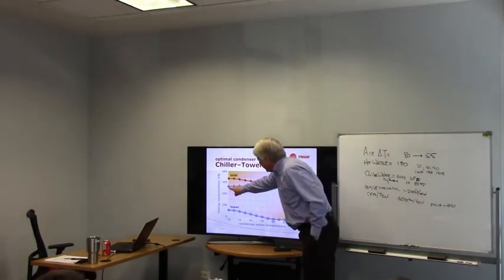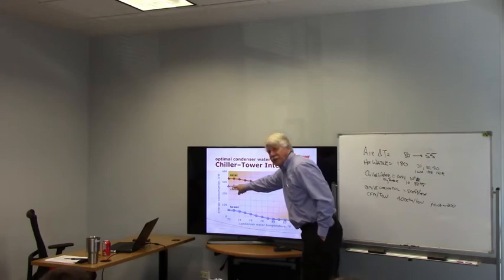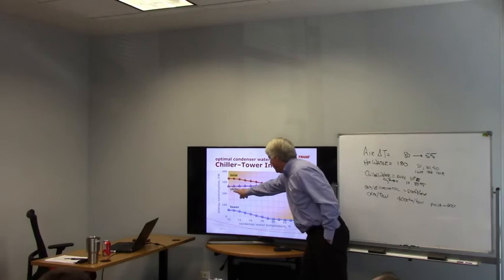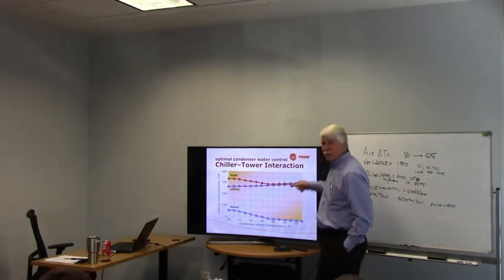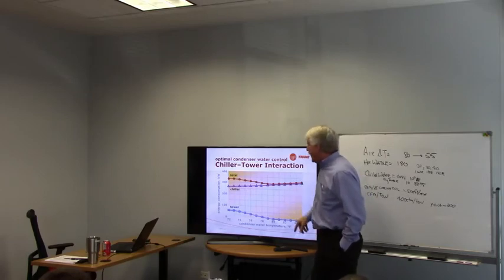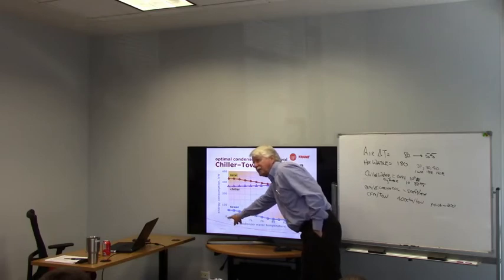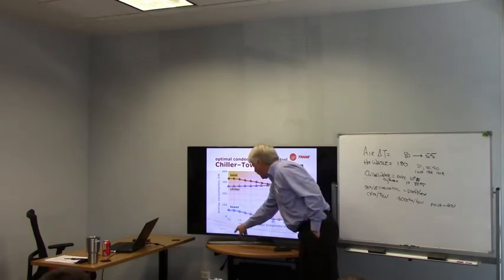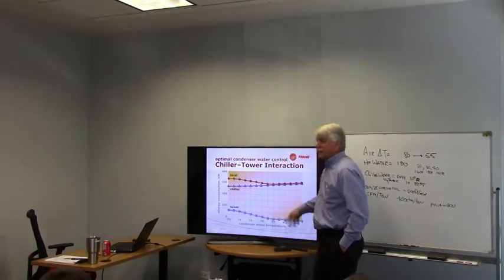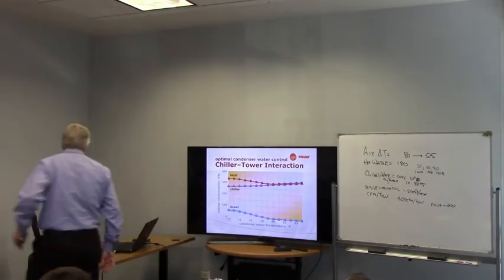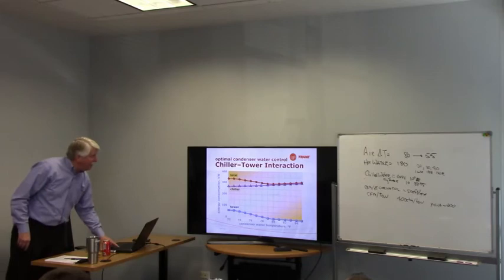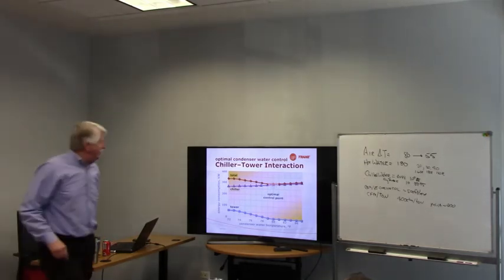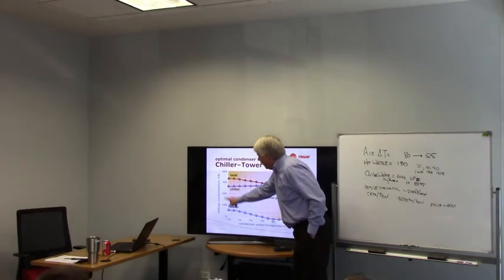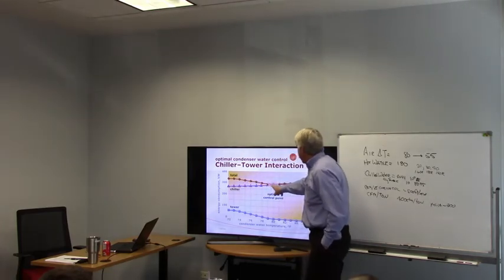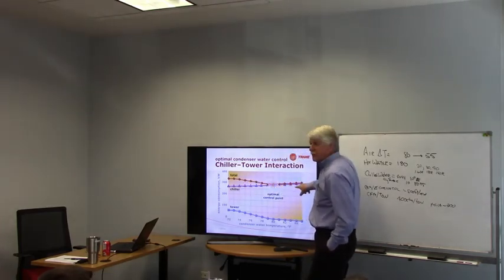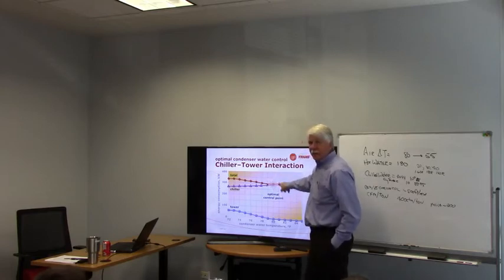When our condenser water is 72 degrees, the chiller's really efficient, okay? So it's got cold water coming in. As the water temperature comes up, the chiller uses more energy, which makes sense because it's doing more work. Now you look at the tower, and down here at 72 degree tower, I'm running the tower fans wide open and moving a lot of air, which is taking a lot of horsepower. As it gets hotter out, it takes less horsepower because I'm not doing as much work. So when you put all that together, you get this. And you can see at real cold tower water, it costs you a lot to operate. But this comes down, and at some point, there's a low point, and then it starts going up. So there is an optimal tower temperature to run.